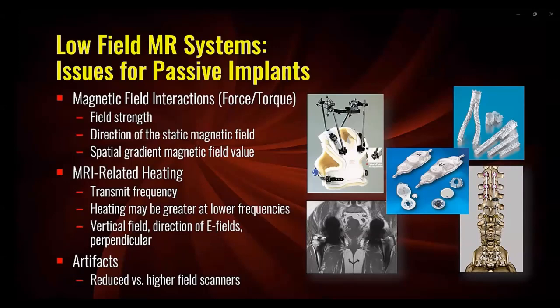For vertical field scanners, consideration should be given to the fact that the static magnetic field is in a vertical direction. With respect to the force acting on an implant, the maximum patient-accessible spatial gradient magnetic field also needs to be taken into account.